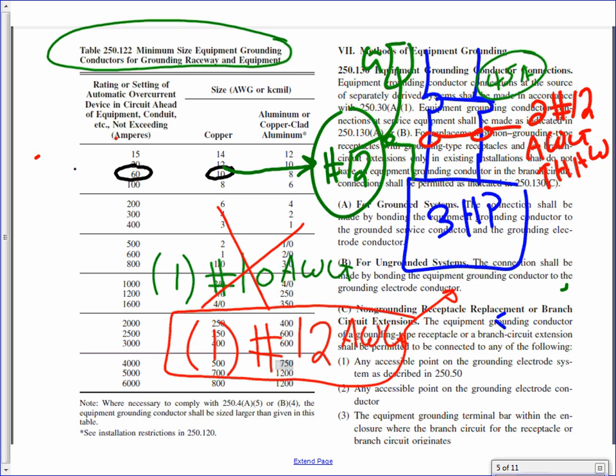Why? Can you guys see the branch? Here's an example of the motor. I have two pole circuit breakers. The two conductors coming to the motor are number 12. We just sized them. The equipment ground conductor came up with number 10. The code says if the equipment ground conductor is larger than the ungrounded conductor, you do not need to go larger, right? So I know my calculation came up with number 10, but I drop it down to number 12 because I do not need more than number 12. Can I have thumbs up, Chad? This is the most confusing part, even for seniors. So always look at the ungrounded conductor, which is the hot conductors. Had these hot conductors been number 8, do you guys hear me? If that was number 8, then this will continue being number 10.